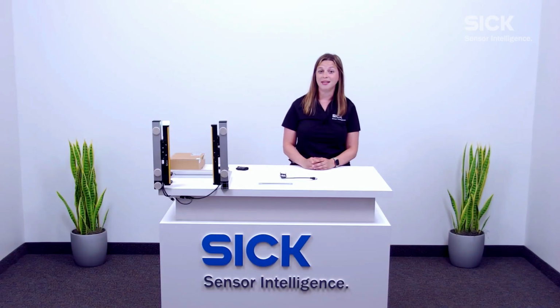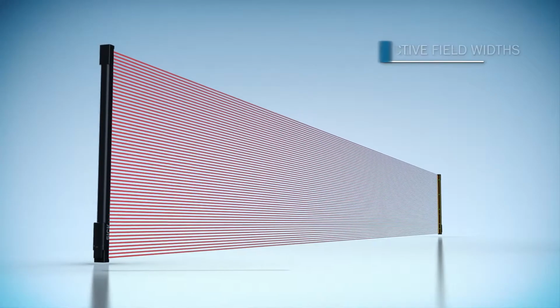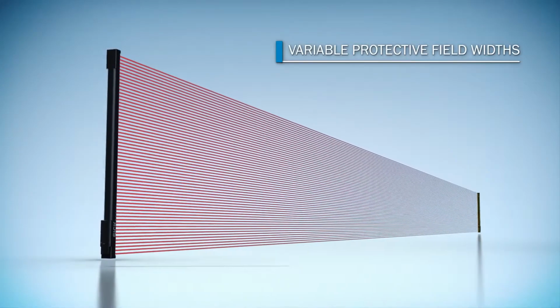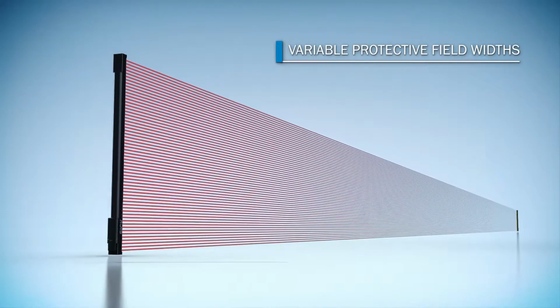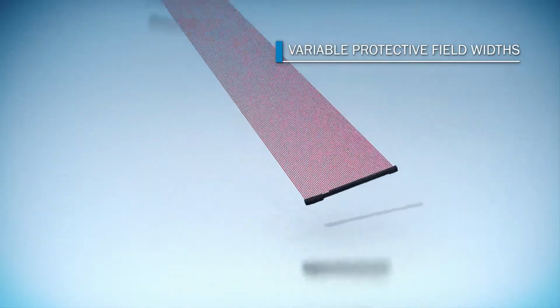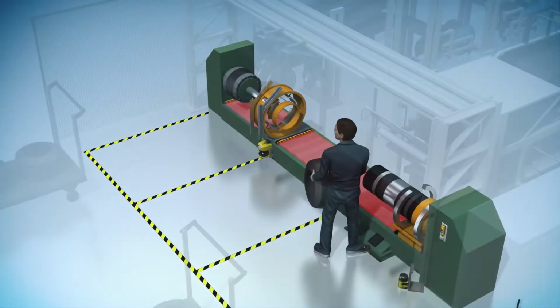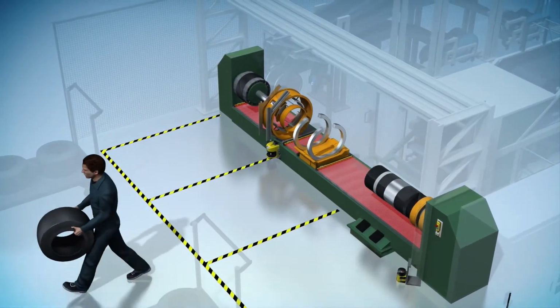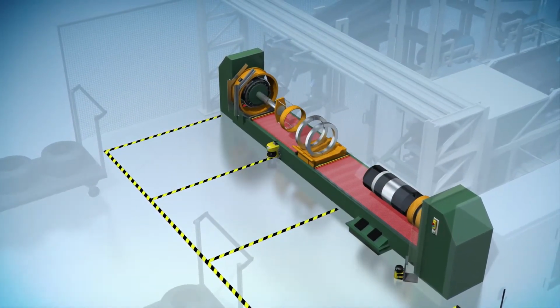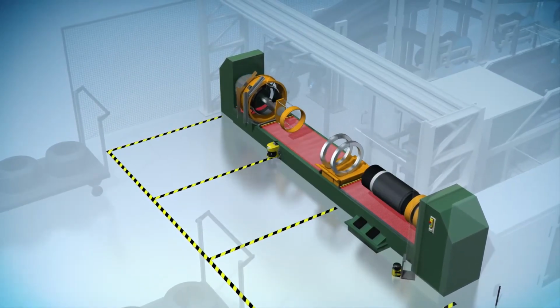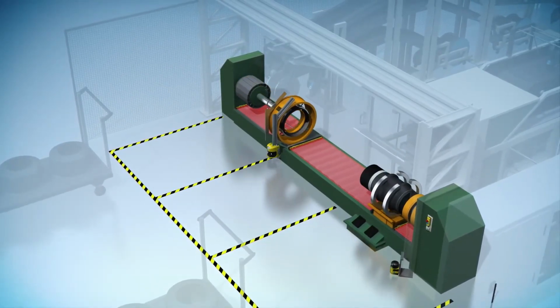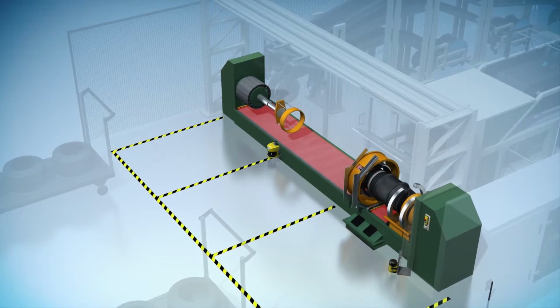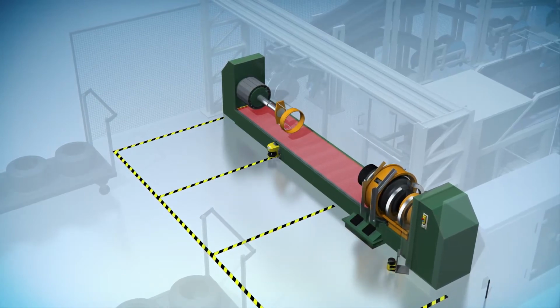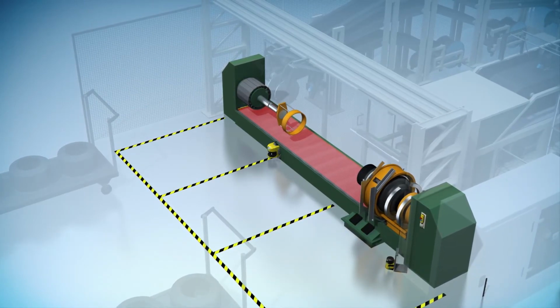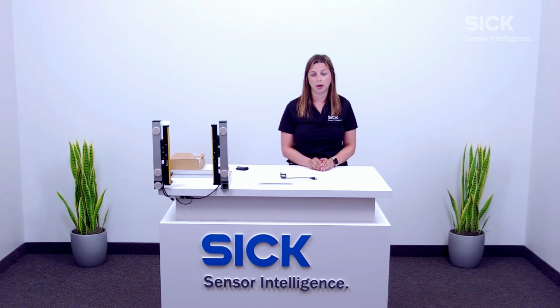I will be discussing a feature called Dynamic Protective Field Width. This is recommended for tire builder machines or machines that typically have parts that are moving and changing their different detection widths. So this is great in instances where you're looking to put on the tire sidewalls. If you have a light curtain mounted to this machine and it's moving in and out, it will automatically calibrate the light curtain so there is no need to have any unwanted process interruptions.